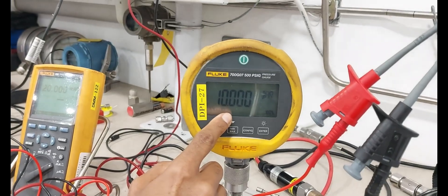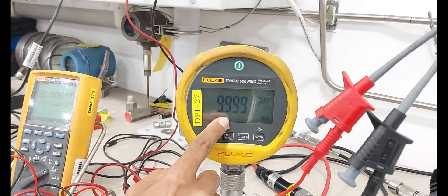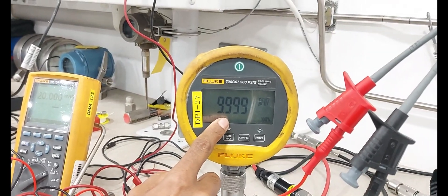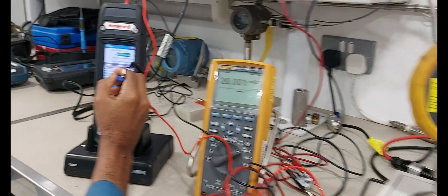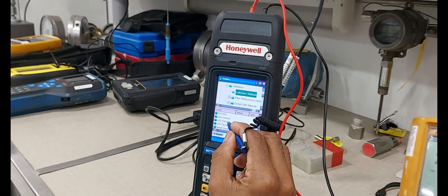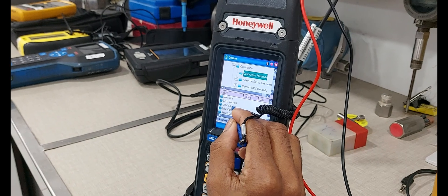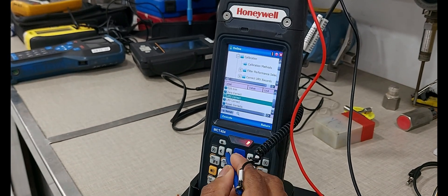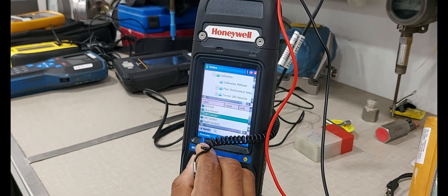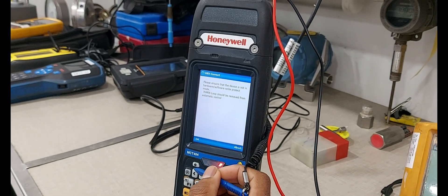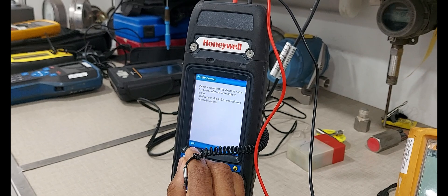We are applying for 10 bar. Okay. Next enter the value, upper sensor trim, execute. Okay.